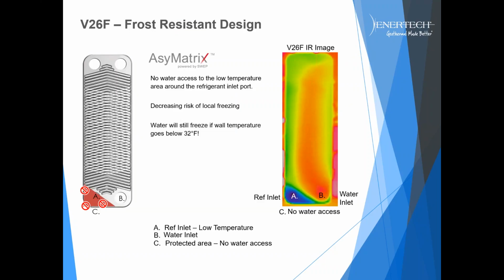The other part that they have really designed into the braze plate, if you notice down on the bottom left, with their distribution piping, they don't allow any water access into the very cold refrigerant inlet. And again, that just alleviates any possible or potential freeze issues. So if there's no water around the coldest part where the refrigerant comes in, there's no way we're going to freeze that water. And so they've done a really good job, again, of designing this asymmetric heat exchanger specifically for the water source heat pump market.